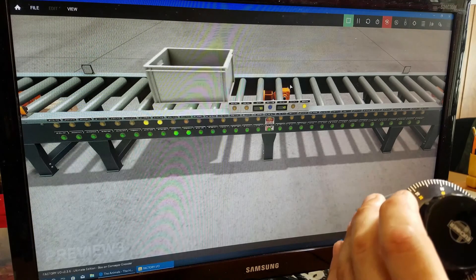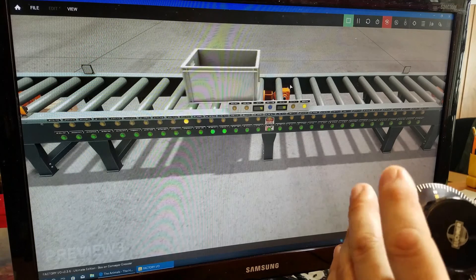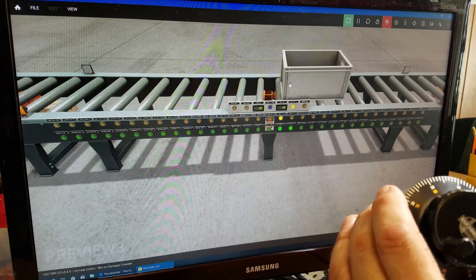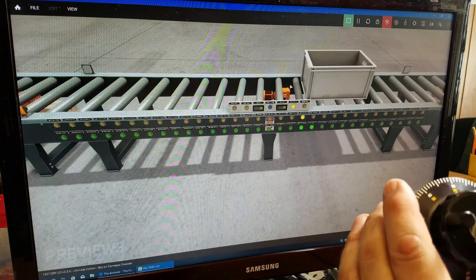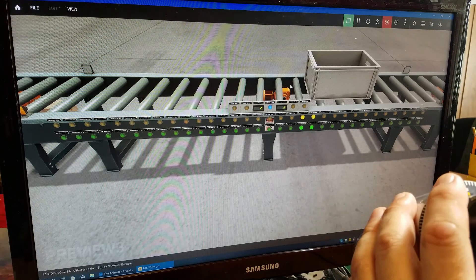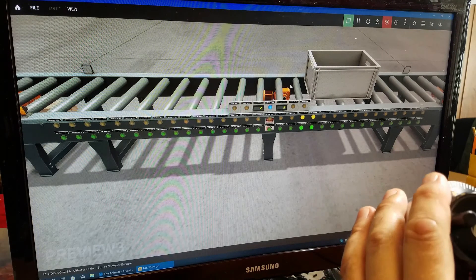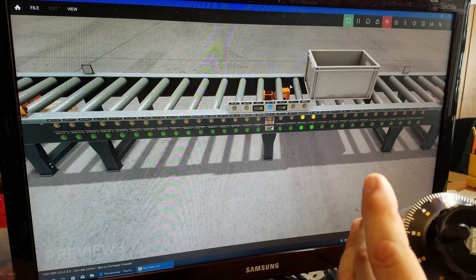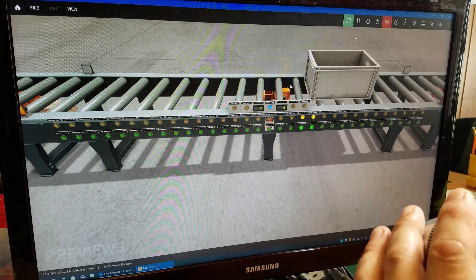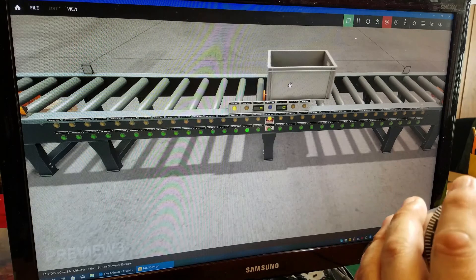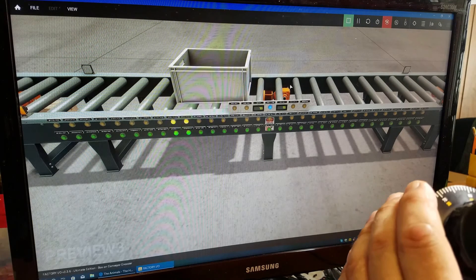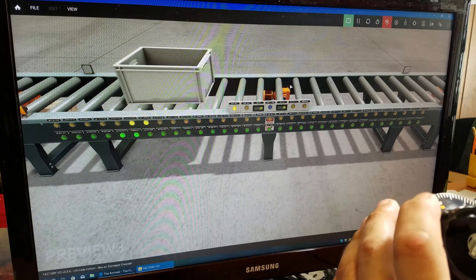In a real machine or a factory, I wouldn't necessarily move a box around on a conveyor using encoders, but this is a good way to play with encoders. Typically, what I'd have is an in-position proximity switch and an approach proximity switch. As the box moves towards the approach proximity switch, it would be at high speed. As soon as it hits the approach proximity switch, it would drop down to low speed, and then stop at the target position. That way, you can run the box at a fairly high speed between points without any position problems once you get to where the box needs to stop.